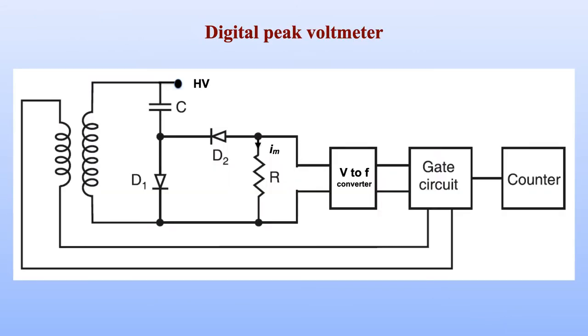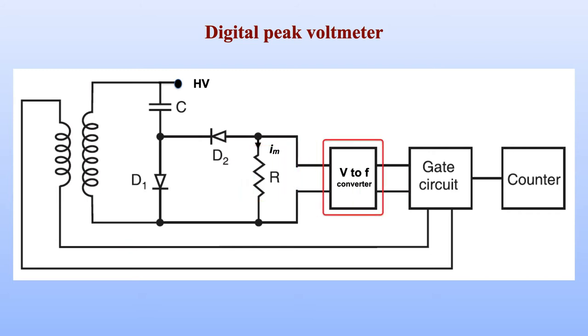This is the second method for measurement of peak voltages for AC. Kindly focus your attention on this diagram. This is a digital peak voltmeter arrangement. It consists of a capacitor connected to the high voltage supply along with a resistance for carrying the discharge current during the negative half cycle through the capacitor. The rectified current flows through resistance R, and the voltage developed across this resistance during the half cycle is converted using a voltage to frequency converter.